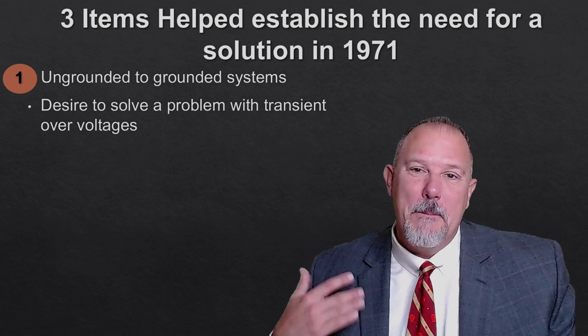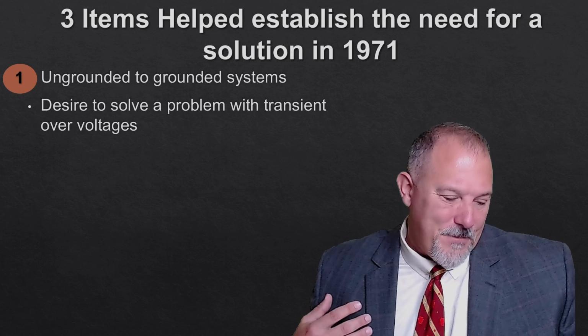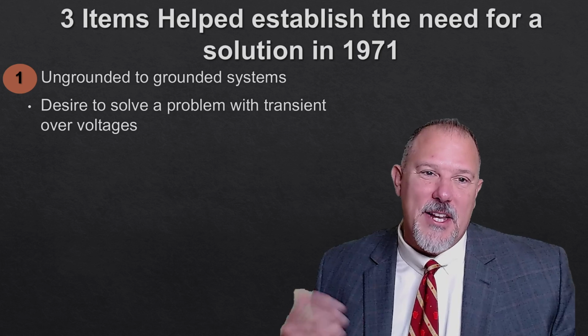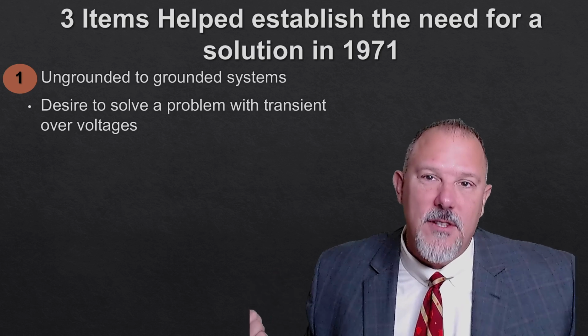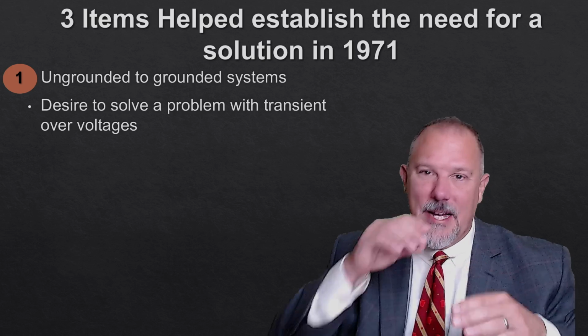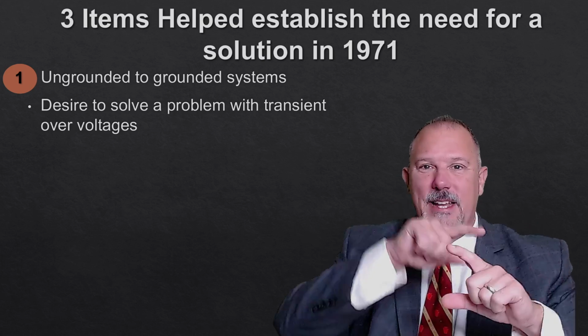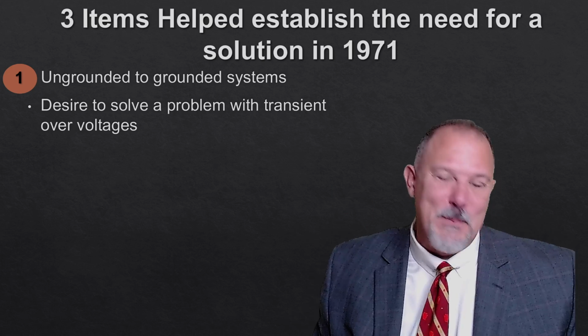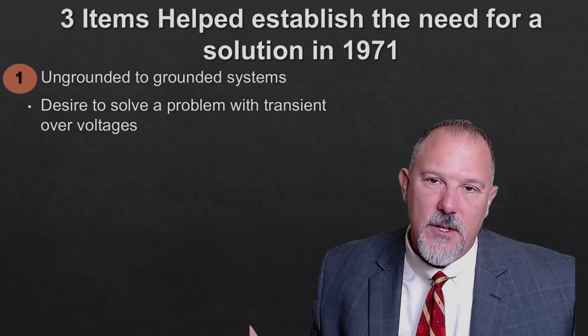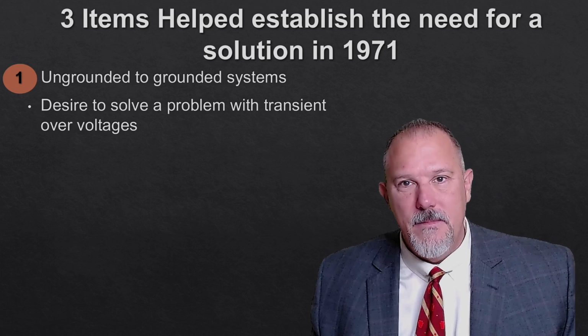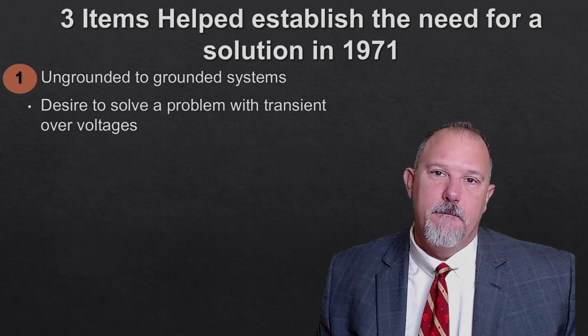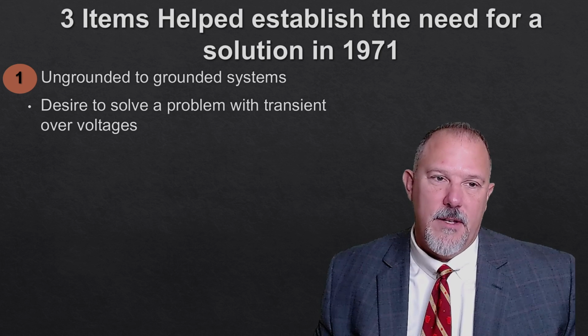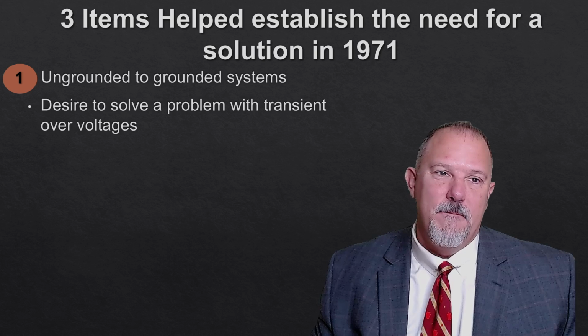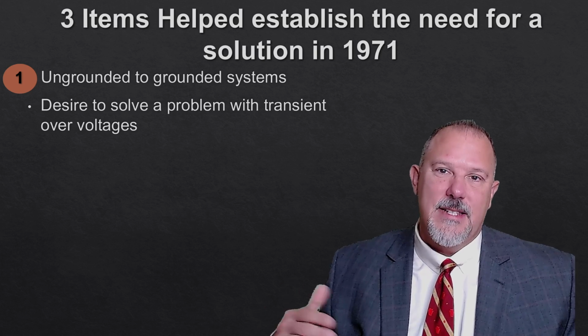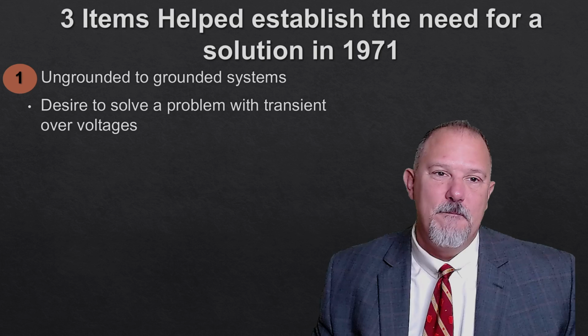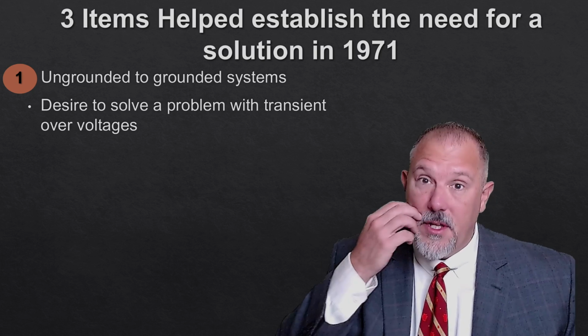And the PE that I worked under got a kick out of me because I called it the spider. I'd say, hey, I went out and looked at the spider today. Because on the one-line diagram, it was big and round and it looked like a large spider. But a zigzag transformer is what they used to ground the system. And that helped with calculating fault currents, and it limited the transient voltages, etc. They also helped limit the available fault currents or the short circuit currents, etc.